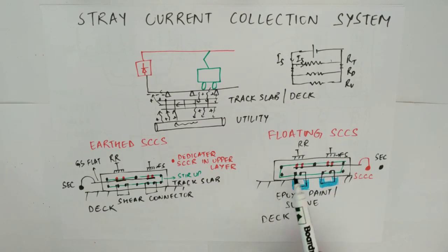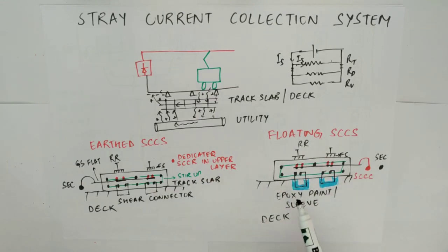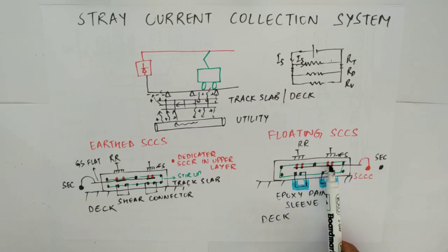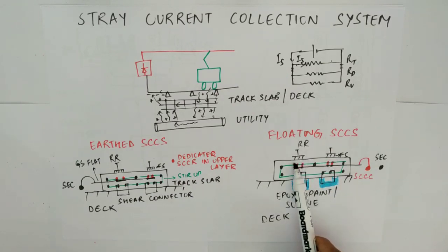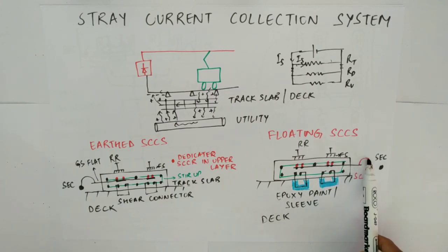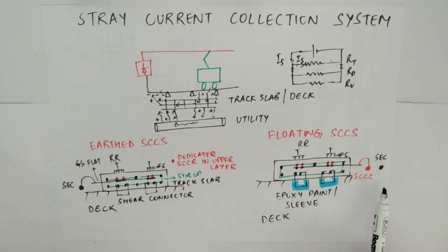So suppose this is your running rail and this is your fastening system. After this, the stray current enters into your track slab and this is your deck. In this case you have some dedicated stray current collection rebars, which are marked in red, and these are your structure rebars marked in black, which are connected together through stirrups. Remember that the dedicated stray current collection rebars must be directly under the running rails so that they catch most of the current. Along with this, we have a galvanized steel flat which is welded to these dedicated stray current collection rebars, and from here it is connected to a dedicated stray current collection cable (SCCC), which is separate from the earthing cable and runs parallel along the track.